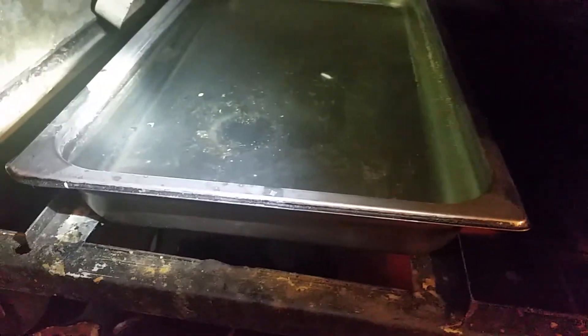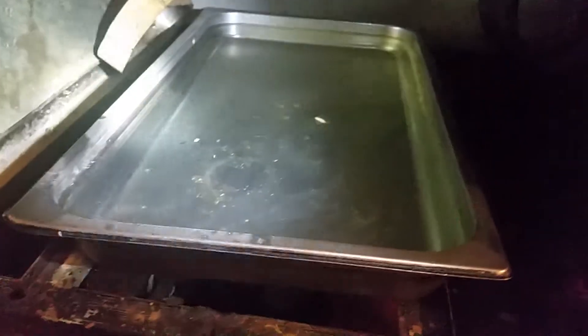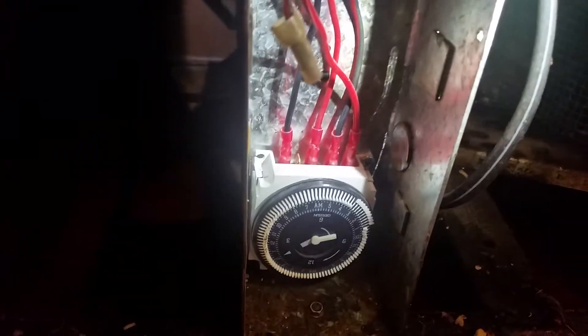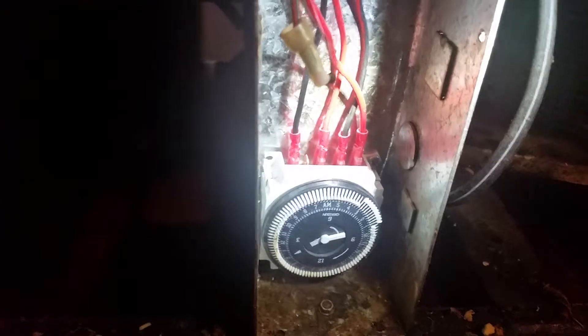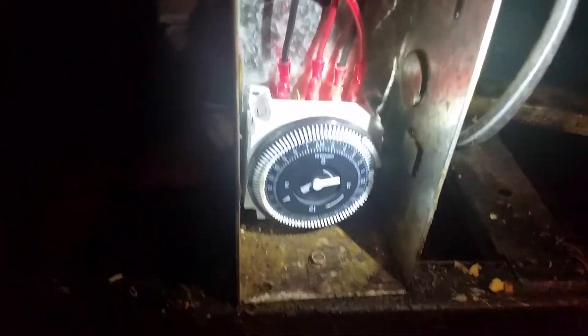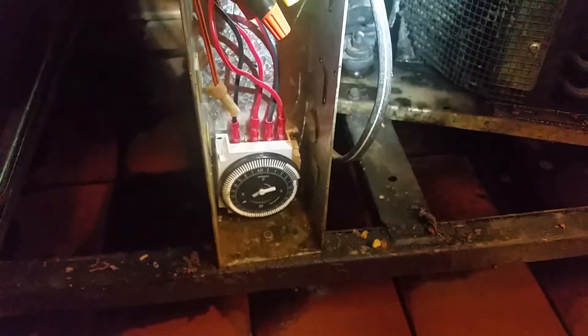You can see the result — all this is water. Since I installed the timer and put it on defrost, it has defrosted completely and now the unit will work again. They will never have this problem anymore. Basically what we did was just install a 120-volt motor timer, and this is the solution for those types of problems when your evaporator coils are getting frozen all the time. Thank you for watching this short video.